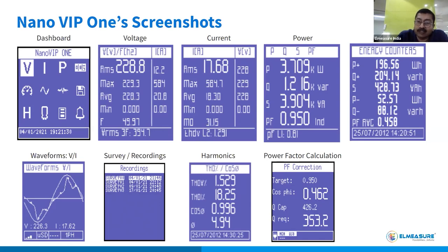Second thing is power factor calculation. We try to manage and maintain the power factor above 0.95 at the incomers, but down the line near the motors, the power factor may not be as good. So there is a provision where you can set a target power factor, and it will tell you what capacitor bank is needed to meet the target of 0.95. This is an example we are showing, one of the features built into the product. It shows how much capacitor bank you can add, what the existing power factor is, what the existing kVAR is, and what kVAR needs to be added.